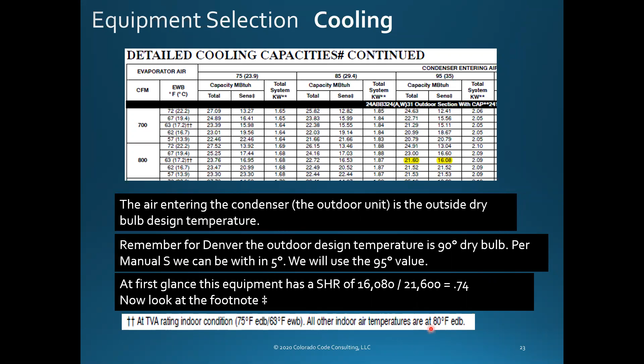Here's the little footnote I was talking about. They used to just give you this one and you had to do a whole lot of math, but now they've got this where it talks about using the 75-degree indoor temperature, which is awesome. Now we don't have to do a lot of extra math because everything else was done at 80, and we just learned why - that's the AHRI standard.